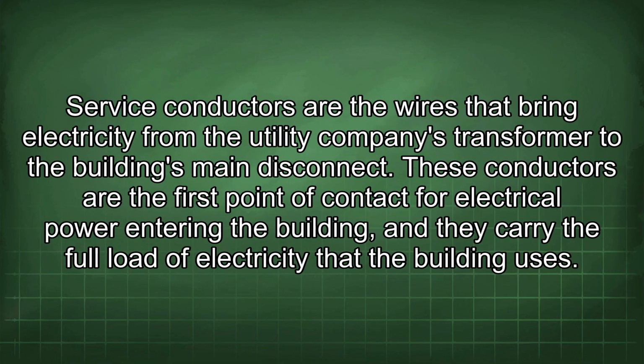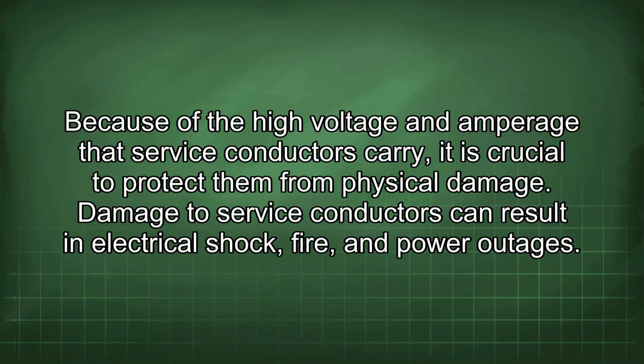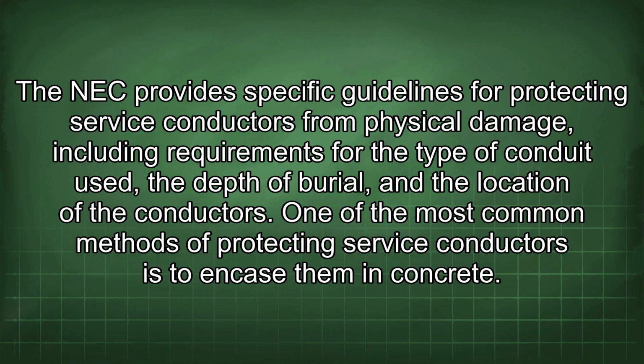Service conductors are the wires that bring electricity from the utility company's transformer to the building's main disconnect. These conductors are the first point of contact for electrical power entering the building, and they carry the full load of electricity that the building uses. Because of the high voltage and amperage that service conductors carry, it is crucial to protect them from physical damage. Damage to service conductors can result in electrical shock, fire, and power outages. The NEC provides specific guidelines for protecting service conductors from physical damage, including requirements for the type of conduit used, the depth of burial, and the location of the conductors.